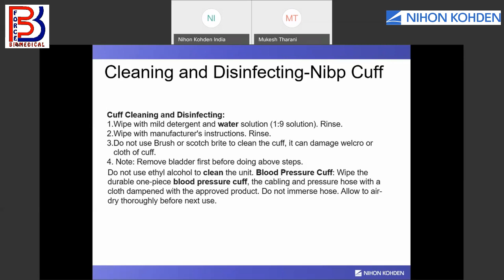It could be harsh on the NIBP cuff. Wipe a durable one-piece blood pressure cuff, cable, and the pressure hose with a cloth damp with disinfectant which is approved by the manufacturer in the manual. Also, do not immerse the hose, and allow it to air dry thoroughly before its next use for the next patient, because this is a reusable cuff and reusable cuffs need to be taken care of very carefully. So it is very much required to disinfect and clean the NIBP cuff.